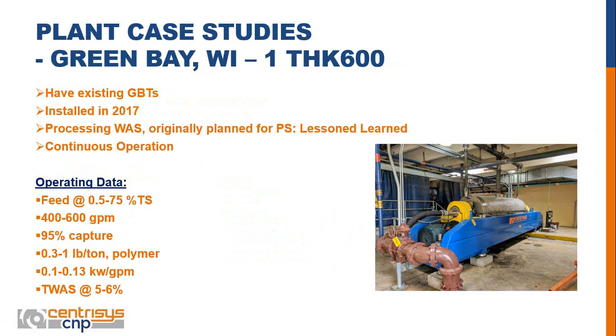Similar to what we ran into with Kenosha, primary sludge was a challenge because of the trash. That was one issue. Ultimately, the grinder in there wasn't cutting the particles small enough, leading to blockages in our feed pipe. We redesigned the feed pipe and got that resolved. But we were still having issues with the cake being too thick to pump, and it was only a problem at times.